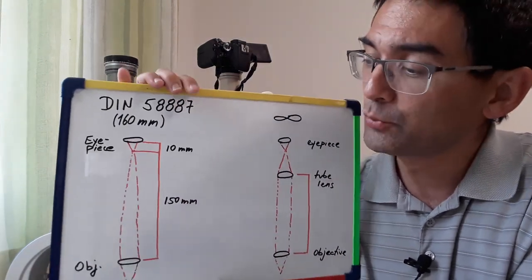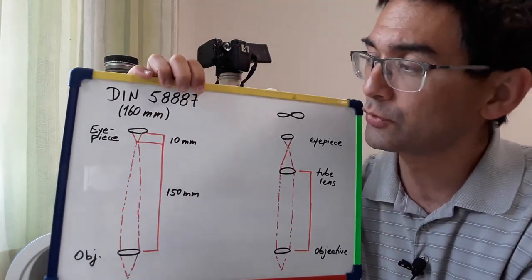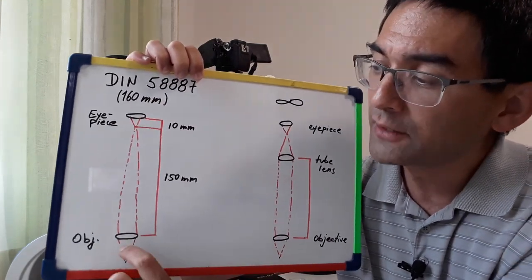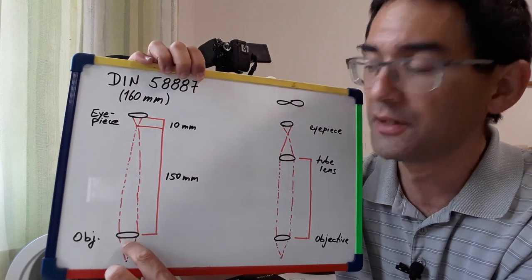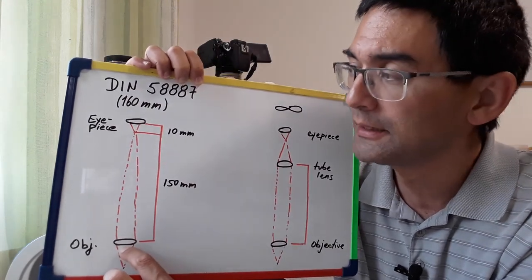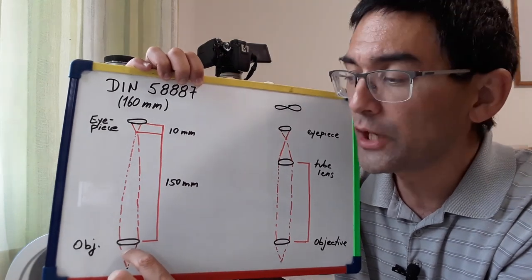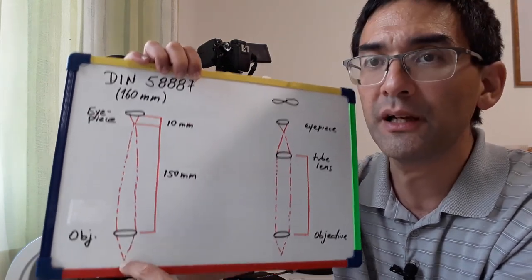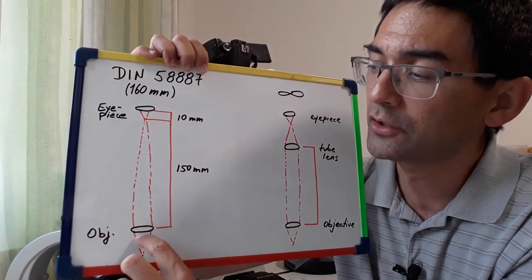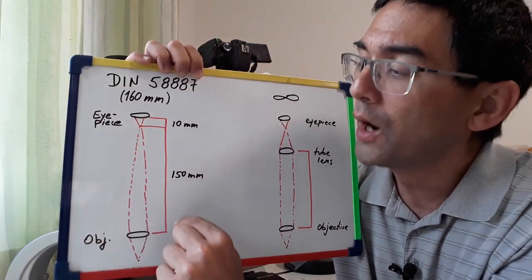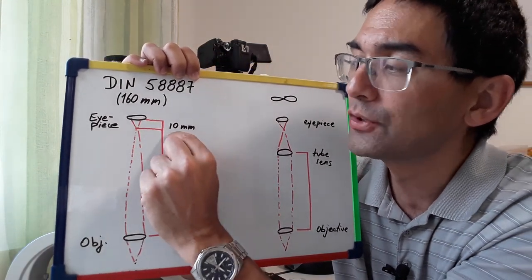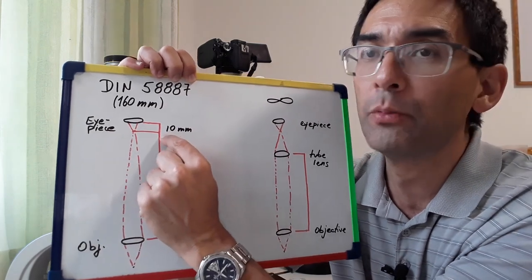I'm going to start off with the DIN objective and what I've done here is I've drawn a schematic diagram of a microscope. The objective lens is supposed to be this one down here. I greatly simplified it and the eyepiece is up here and what this objective lens does is, this is the specimen down here, it creates an image 150 millimeters into the tube of the microscope.